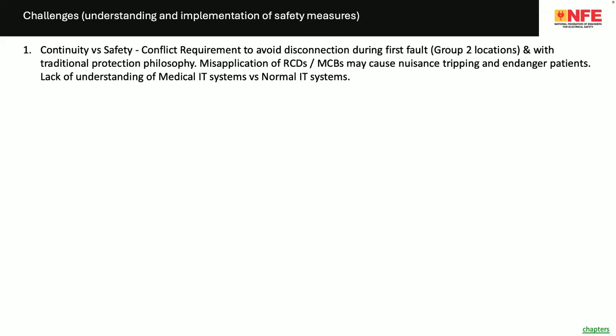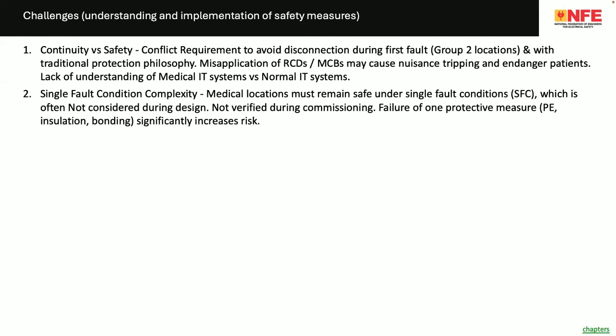If you put a normal IT system, for example, you are using a UPS, at the output of the UPS you put an isolation transformer, put some monitoring devices and start calling this a medical IT system. No, wrong. This will create fire. You have to go for a medical IT system where the leakage currents are extremely low.